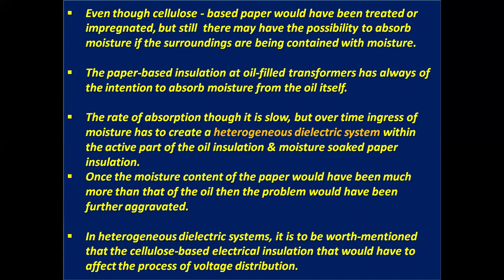Even though cellulose-based paper is treated or impregnated, there is still the possibility of it absorbing moisture if the surroundings contain moisture. The paper-based insulation in oil-filled transformers always tends to absorb moisture from the oil itself. The rate of absorption is slow, but over time, ingress of moisture creates a heterogeneous dielectric system within the active part, of oil insulation and moisture soaked paper insulation. Once the moisture content of the paper becomes much more than that of the oil, the problem is further aggravated.